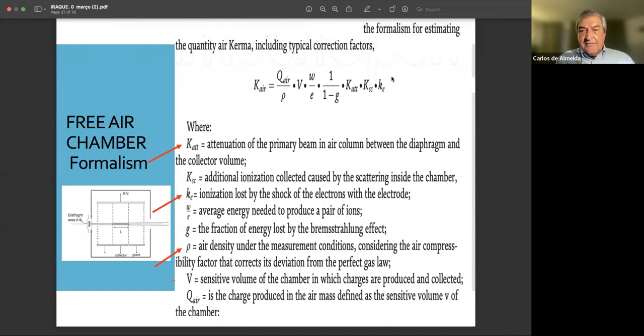For instance, the air chamber requires a number of factors and parameters in order to transform what you measured into the real quantity that you want. In this situation, you have this equation here. The most important ones are the attenuation of the primary beam in the column between the diaphragm and the collecting volume. We have some attenuation here. Also, you have the ionization loss by the electrons in the electrodes. Also, you have the air density, which depends on the temperature, pressure, and also the humidity.